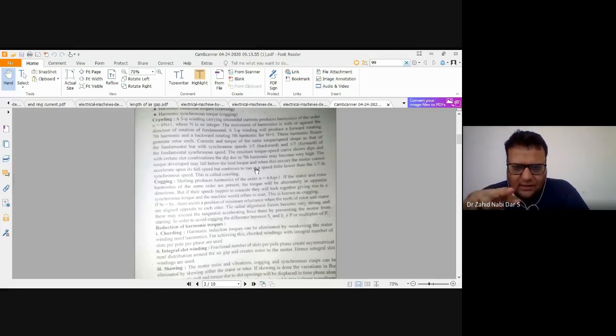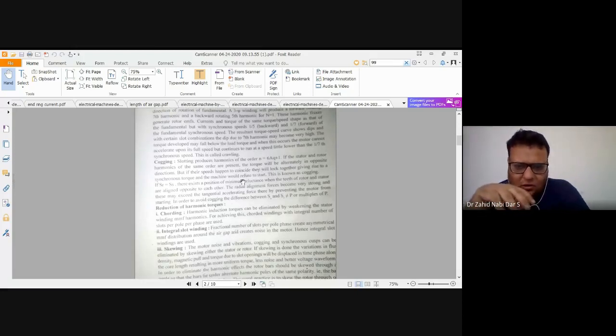Now there is another phenomenon called cogging. Cogging is also called magnetic locking. In cogging, slotting produces harmonics, and if stator and rotor harmonics of the same order are present, how would they be present? It would happen when the stator teeth and rotor teeth are either equal in number or are integer multiples of each other. Then whenever magnetic flux is established in the stator teeth, there is a mutual induction in the rotor, so they lock with each other and become in synchronism with each other.